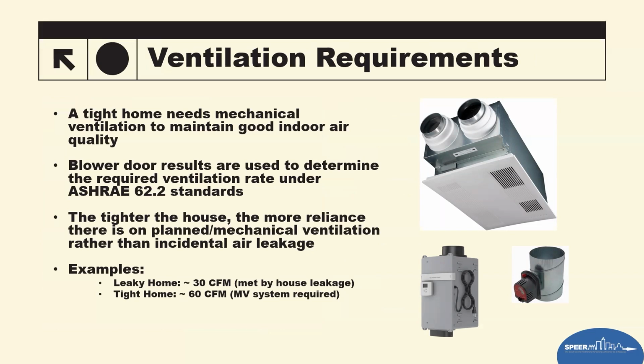And of course, ventilation requirements. I won't go deep in the weeds with ventilation because we've had several webinars about it. But a tight home needs mechanical ventilation for good indoor air quality. We talked about what a contamination is. It's a long list of what is considered a contamination. New houses have off-gassing from new construction materials, and you want to either remove that or dilute that so it doesn't have the parts per million high enough to harm anyone who has respiratory issues or ailments in the building. Blower door results are used to determine what's required for the ventilation rate under the ASHRAE 62.2 standards. The tighter the home, the more reliance we have on planned mechanical ventilation rather than just uncontrolled incidental air leakage. For example, as we had a few slides ago, a leaky home is 30 CFM, met mostly by the house leakage, and a tight home is 60 CFM.